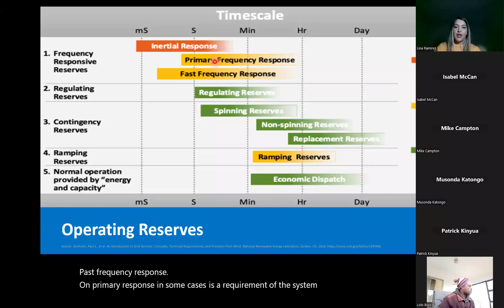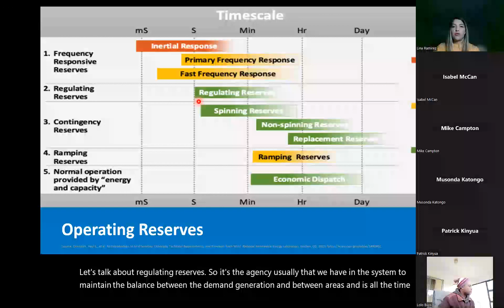Let's talk about regulating reserves. This is usually the AGC that we have in the system to maintain the balance between demand and generation, and between areas. It's sending commands every 4 seconds to the plants connected to the AGC to maintain that balance between generation and demand.